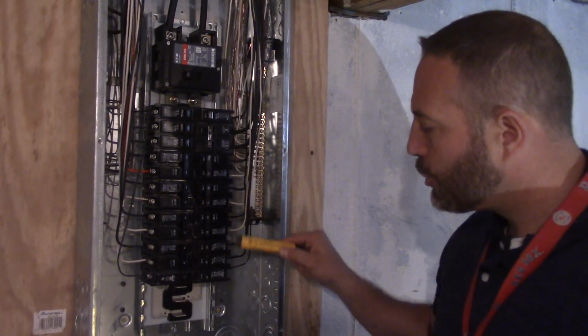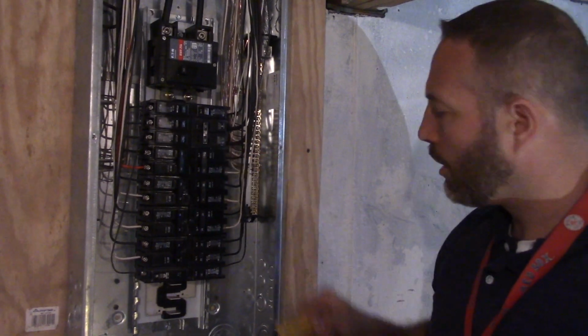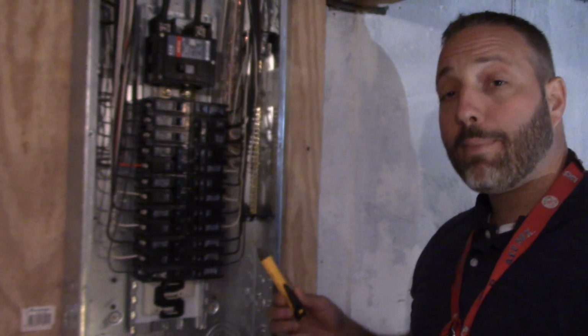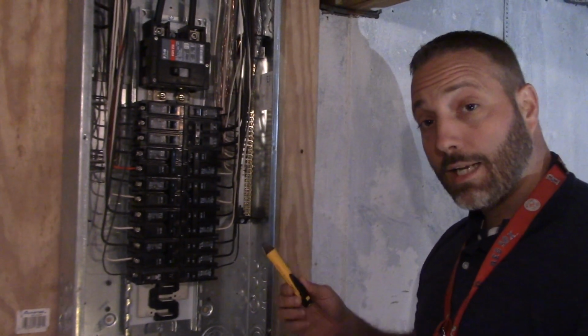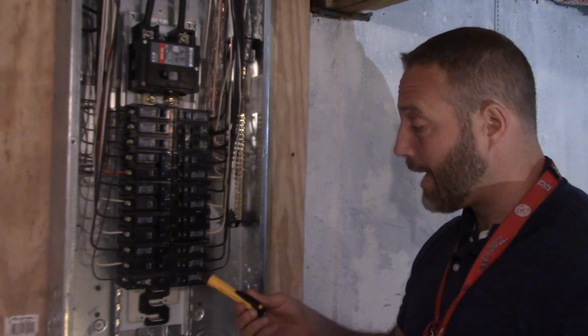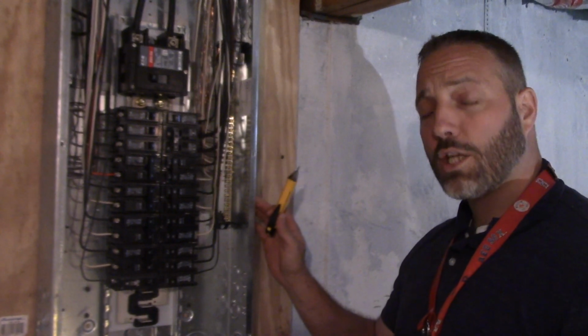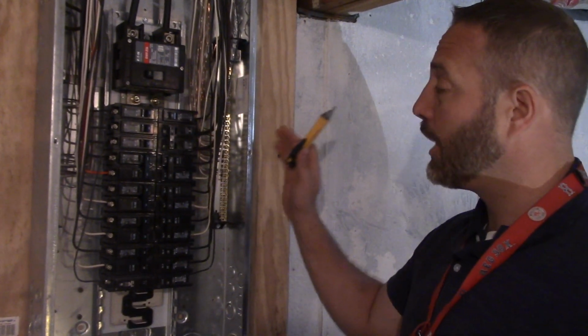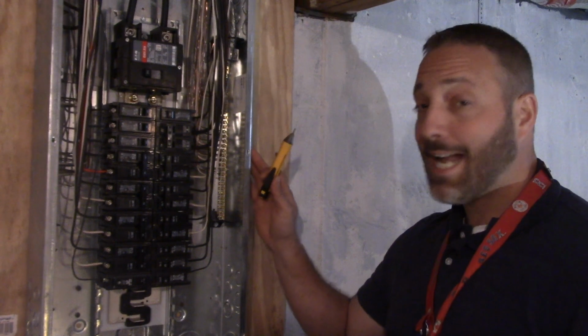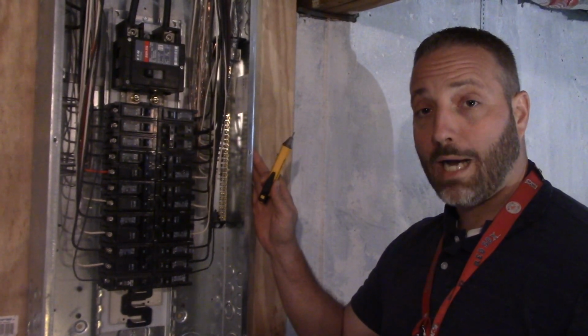All right, so by individually making sure that the wire sizes are correct with the breaker, that means the possibility of any overheating of the wires is not possible. Now, one of the things that you have to make sure is that an electrical panel is not a distribution box for power.